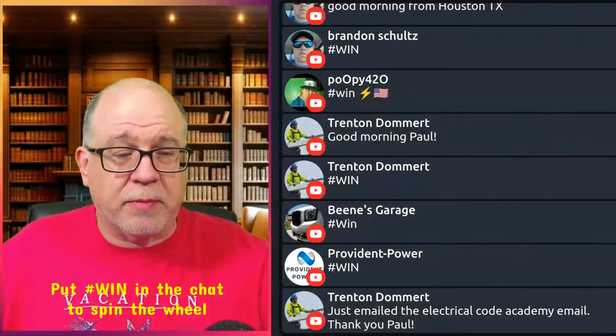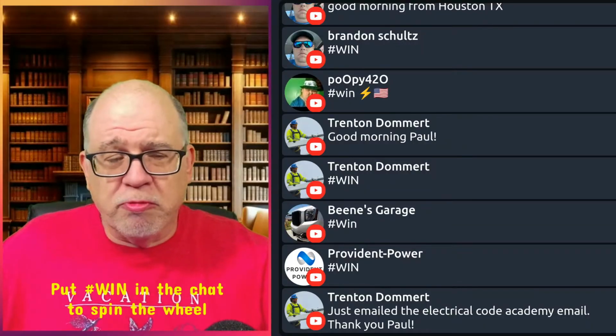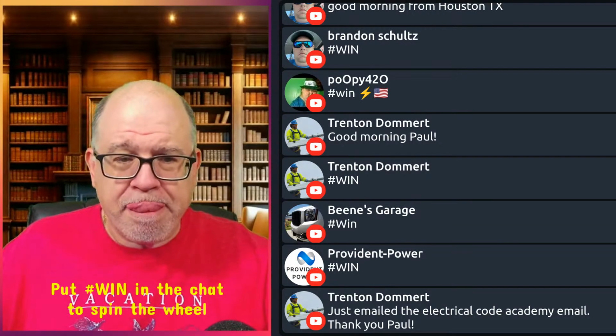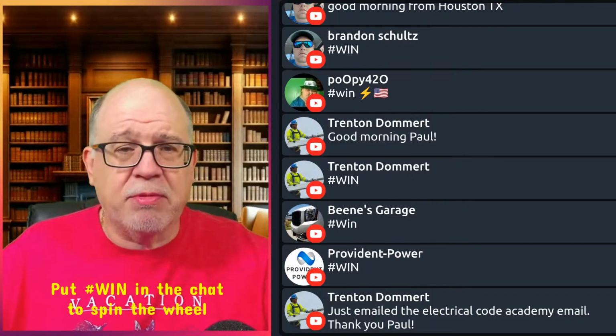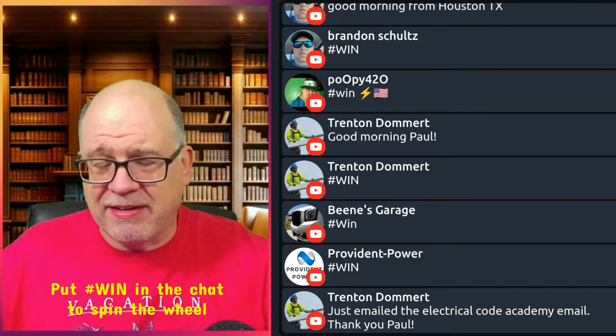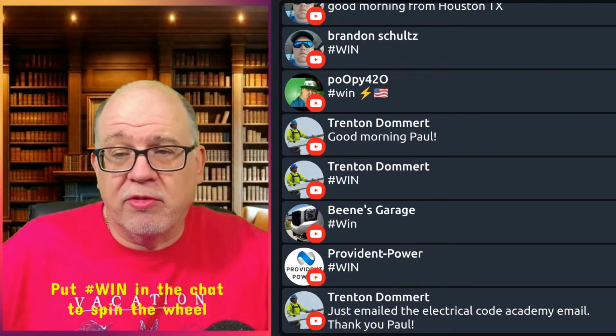I just mentioned this because people ask me that. Can you re-identify a white conductor as a hot? You can in a cable assembly. You cannot in a raceway. People say, well, why? Because that's what the code says.